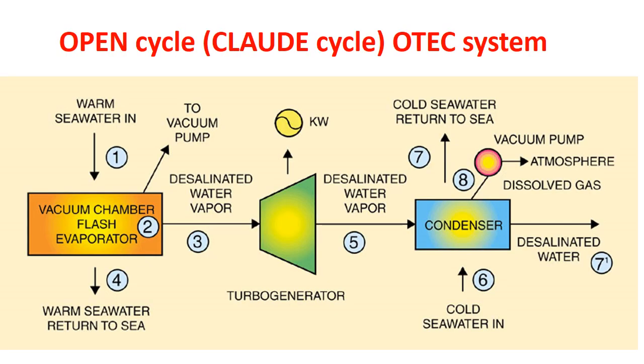The first one is the open cycle OTEC system. The open cycle consists of the following steps: flash evaporation of a fraction of the warm sea water by reduction of pressure below the saturation value corresponding to its temperature; expansion of the vapor through a turbine to generate power; heat transfer to the cold sea water thermal sink resulting in condensation of the working fluid; and compression of the non-condensable gases to the pressure required to discharge them from the system. In the case of a surface condenser, the condensate or desalinated water must be compressed. This is the open cycle OTEC.